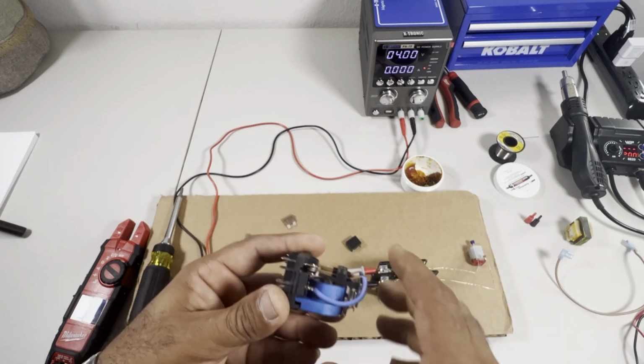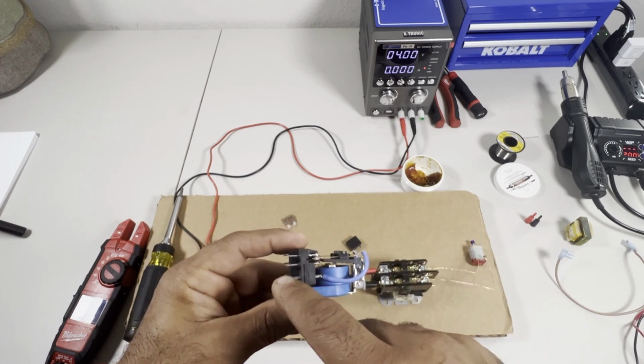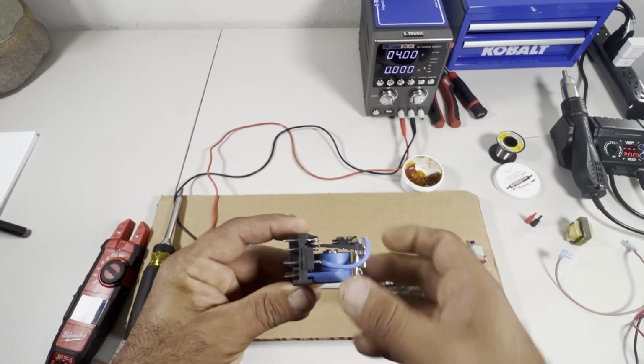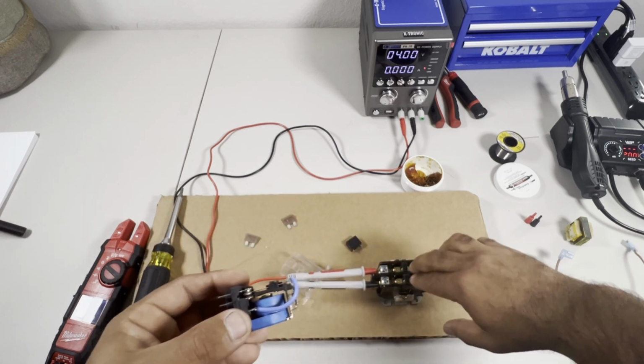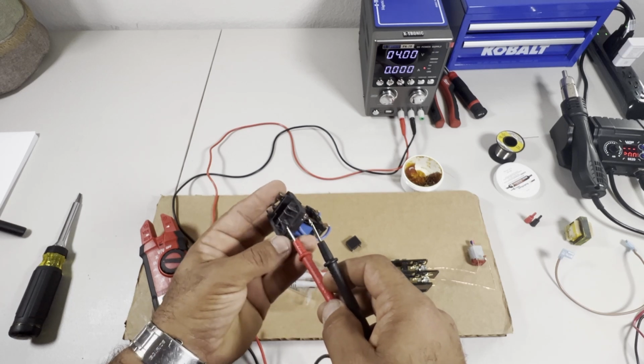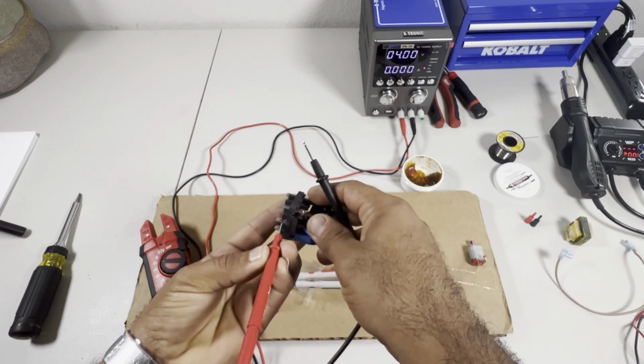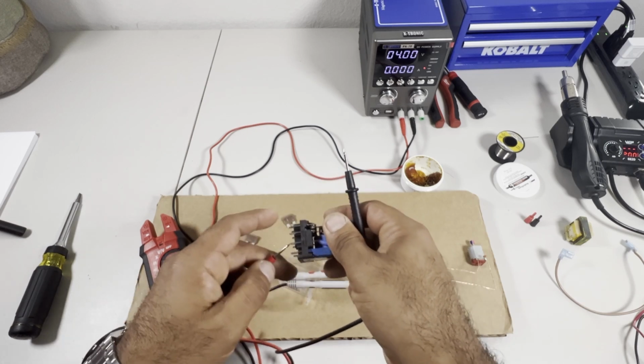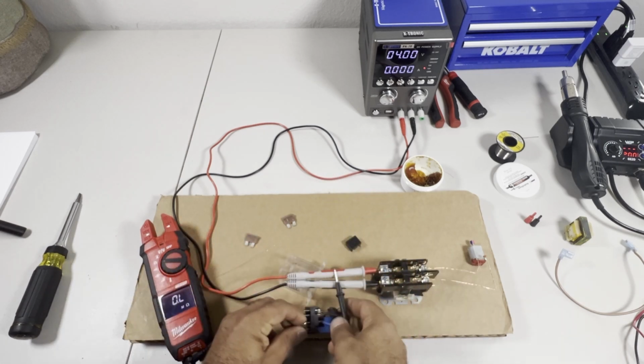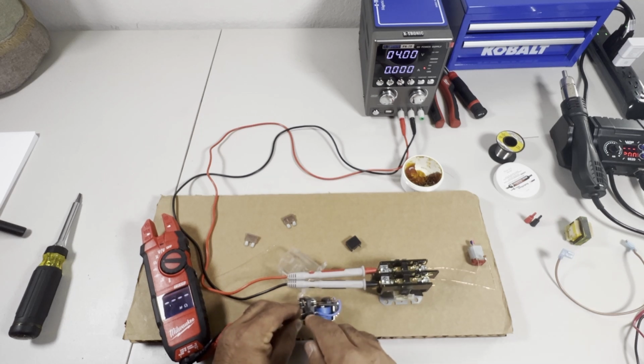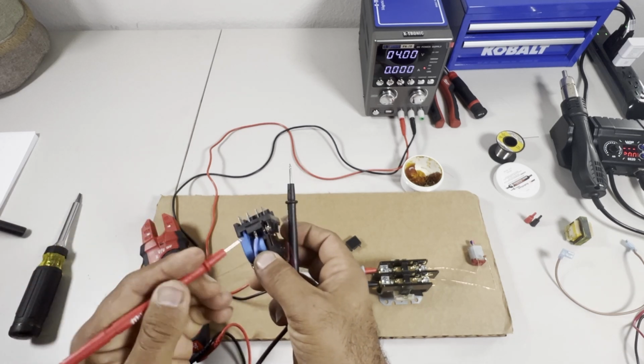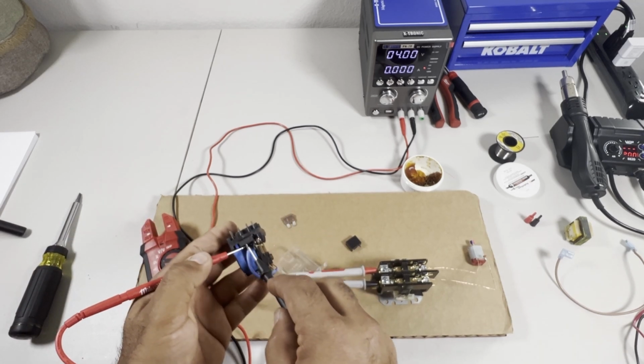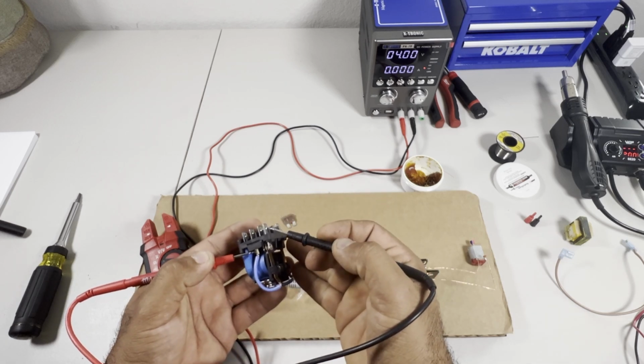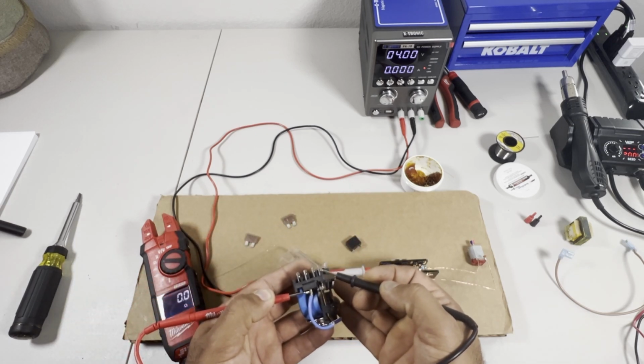Now, what does that mean? Normally closed is the one that is closed when the relay does not have any power applied to the coil. Imagine it's going to be like this all the time. The common terminal is the blue one, and normally closed is on the top. Let's see if we can get a good reading. As you can see, it's reading 0 ohm between this one, which is going all the way through, and this one, which is coming out.